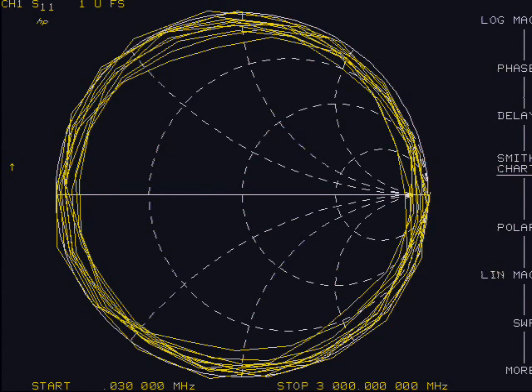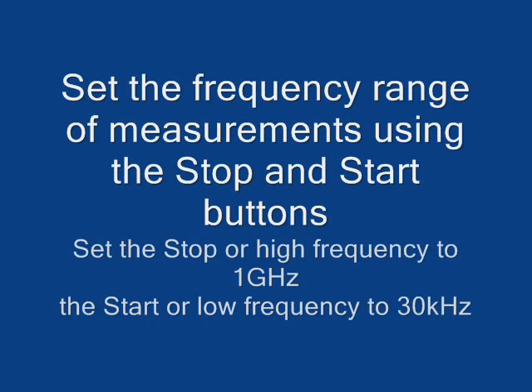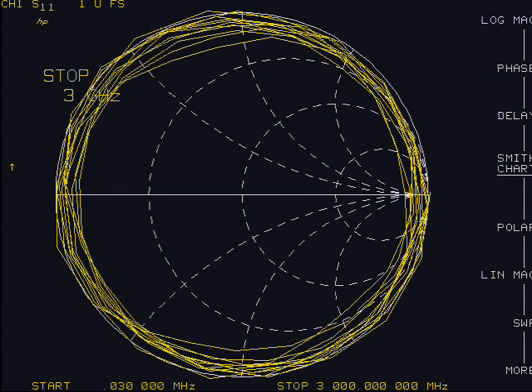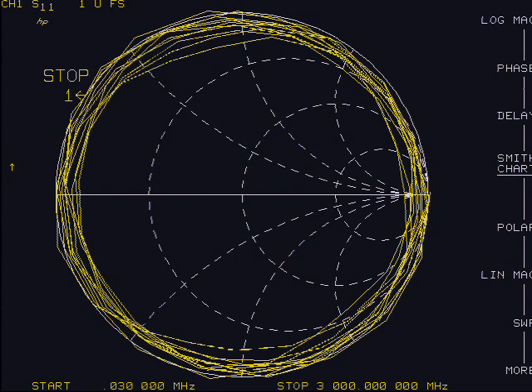Set the frequency range of measurements by setting the stop frequency using the stop button. The unit defaults to 3 GHz, but we will use 1 GHz in this exercise. Use the keypad, 1 G slash N keys for 1 GHz. G for gigahertz, N for nano, which is the inverse of giga.